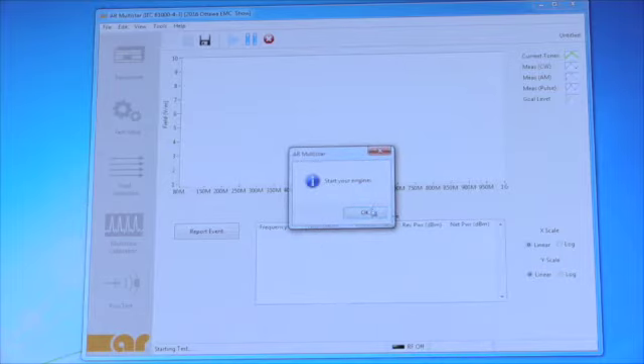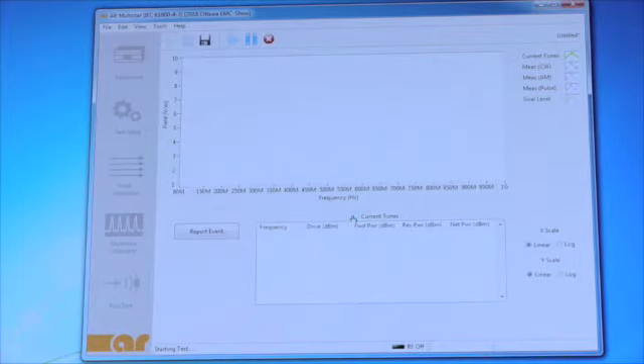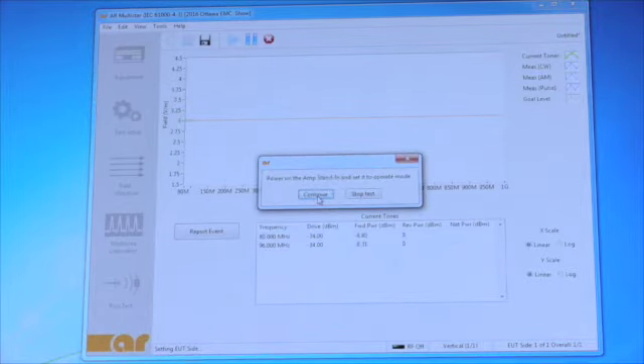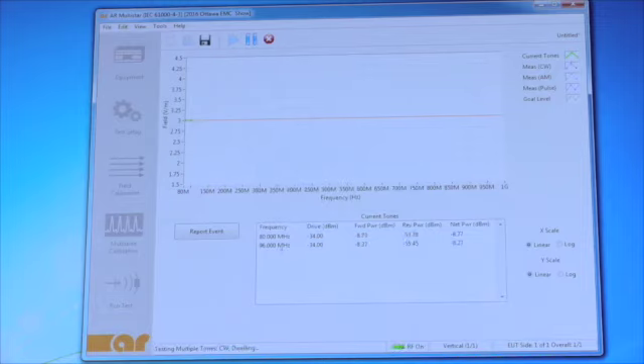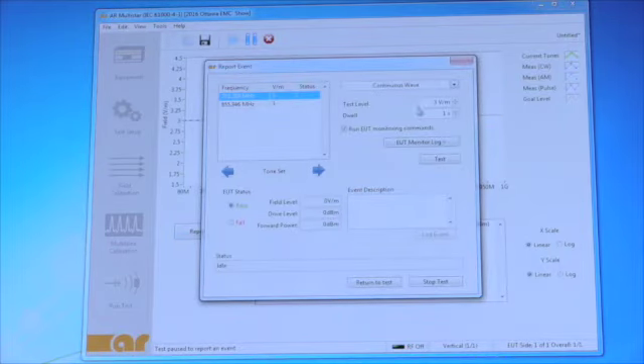Now when it starts, it prompts you again. And now it puts up the first 2 tones. Now you can see how fast it's going through here. Yeah, we're only using 2 tones because we don't have an amplifier. Right, but if there was a problem, you can hit report event, and then you can manually go in here and change. You can select which tone it is. So you can go back to the traditional way of testing. You can select the test level, you can set your dwell, and then you can just hit test here, and it will test it.